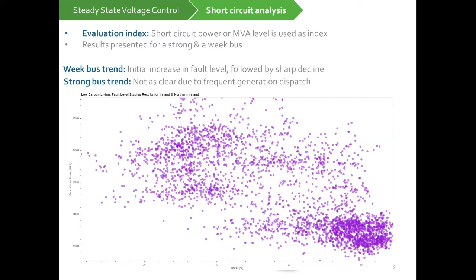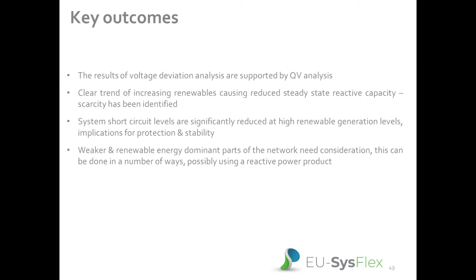The key outcomes of our analysis on steady state voltage are that the results of QV analysis and steady state voltage deviation analysis indicated a clear trend of increased renewable generation causing a reduced steady state reactive capacity. A steady state reactive capacity scarcity is therefore identified. The system short circuit levels are also significantly reduced as renewable generation increases. This may have implications for system protection as well as transient stability. Weaker and renewable energy dominant parts of this network need consideration. This can be done in a number of ways, possibly through a steady state reactive power product as well.